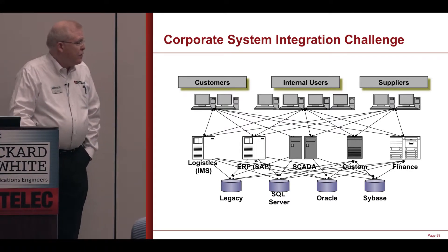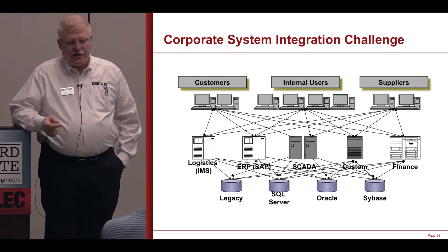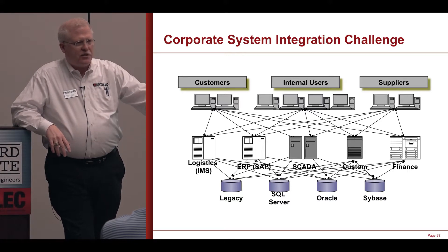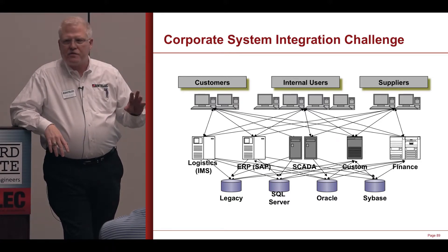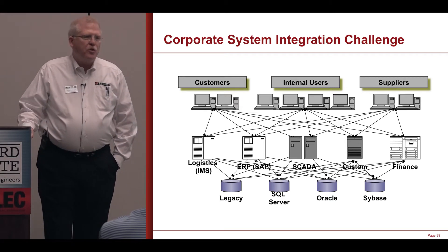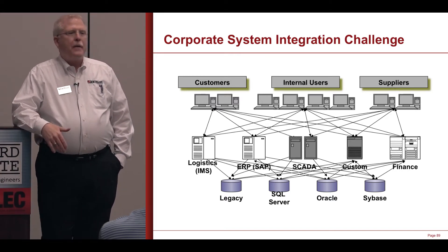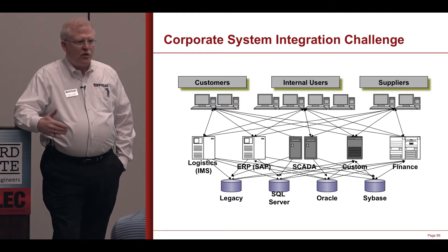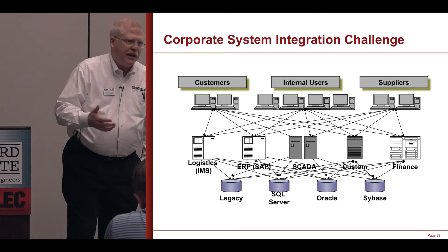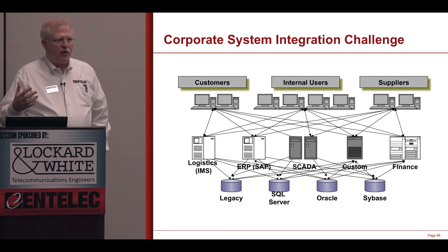This is a big challenge. Historically, SCADA has been isolated — it existed behind a firewall in the process control network and didn't touch any business systems, and there are reasons that's been sustained from a cybersecurity standpoint. The threat is escalating. You can download tools off the dark web to do man-in-the-middle Modbus attacks and spoof a controller — you can actually overflow a tank while showing operators a level that appears normal. Five years ago that wasn't true. In terms of the cybersecurity threat, it's escalating.